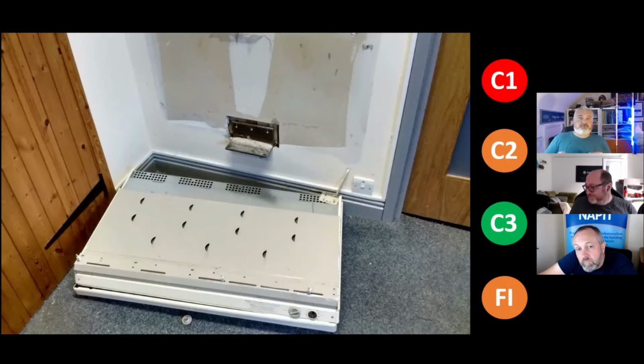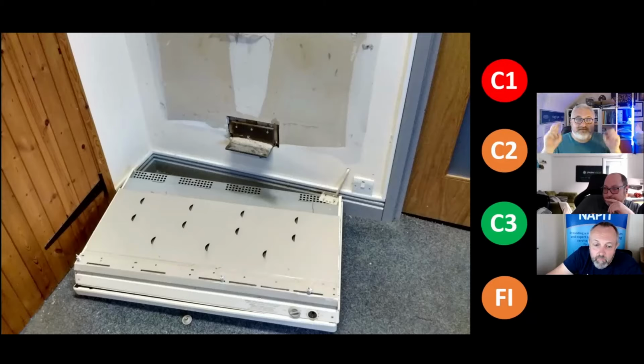But again, as we said in the last one, Dave, just looking at a picture without being there is only 50% of the facts you can see. You have to use more than just your eyes. You wouldn't want to touch it because, absolutely right, if there's strain on the connections, it's fallen off, disconnected, a line conductor has made the case live - absolutely, all day long, C1. So use your non-contact pen - bang, if it's live, C1, absolutely. But as you can see, someone switched it off and took a photo. So you've got to code it based on all the senses, not just what we see. And this is why photographs can easily lead to an argument, where what they should do is lead to further investigation in the mind. Right, let's move on.